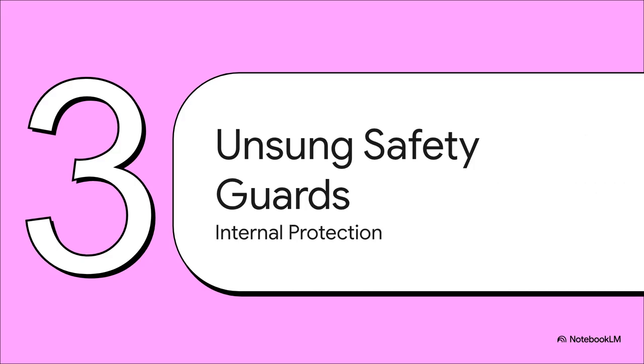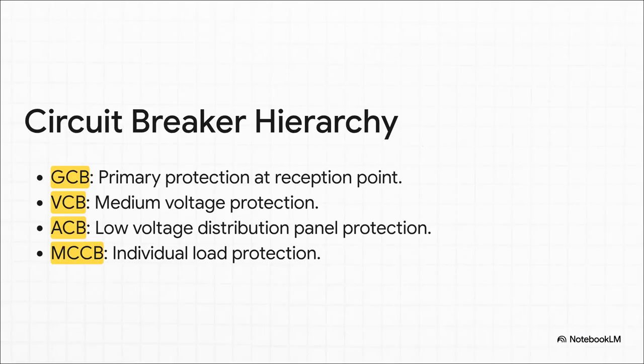But what if the problem isn't outside the data center? What if it's inside? A short circuit or an equipment overload could be just as devastating. And that's where another layer of protection comes in, this kind of internal safety net. Think of this like security checkpoints in a building. You have these massive circuit breakers guarding the main power entrances, and then you have progressively smaller ones protecting each floor, each room, and finally each individual server rack. This hierarchy is so important. It means if one single piece of equipment faults, its specific breaker trips, and that immediately isolates the problem. It doesn't cascade and take down the entire system.